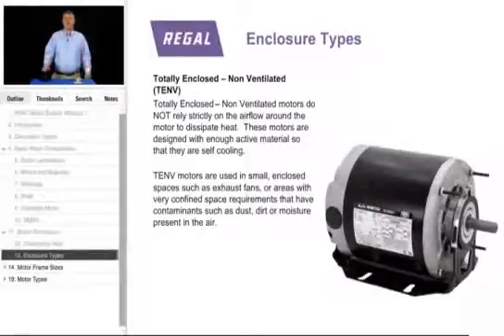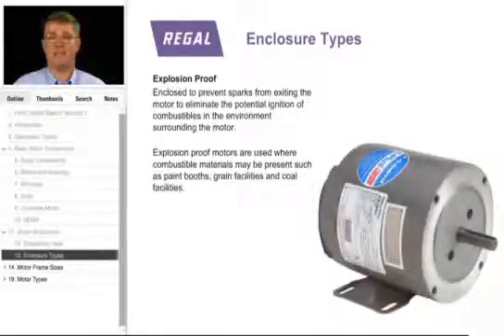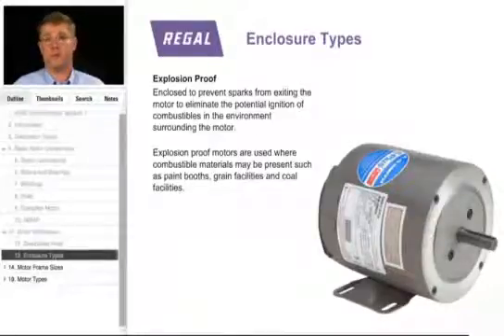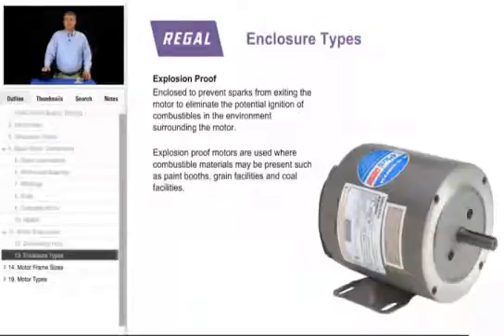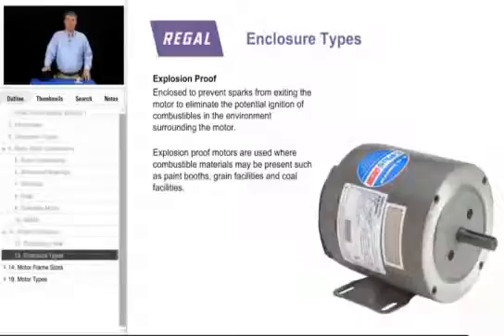The last type of enclosure we talk about is explosion proof. This type of motor must contain a spark inside the motor to not allow any flammable or combustible materials to explode or catch fire. These applications we typically see in paint booths, grain facilities, coal facilities, where any combustible material may be present around the motor.